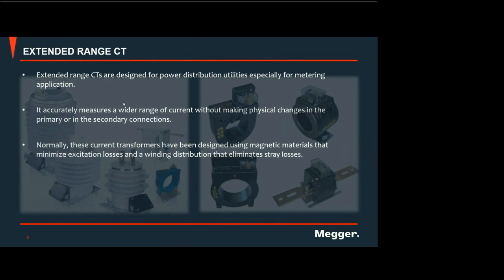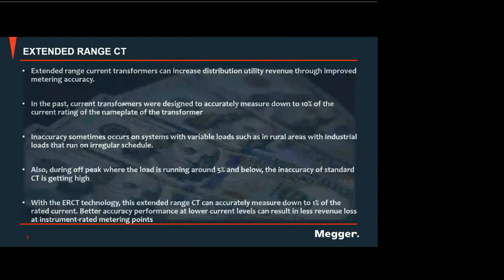This extended range has a better accuracy than the standard one. Normally, these current transformers have been designed using magnetic materials that minimize excitation losses and a winding distribution that eliminates stray losses. Extended range current transformers can increase distribution utility revenue. So we are talking of money here. Of course, the more accurate the CTs that you have, the more revenue you can have, the more money.